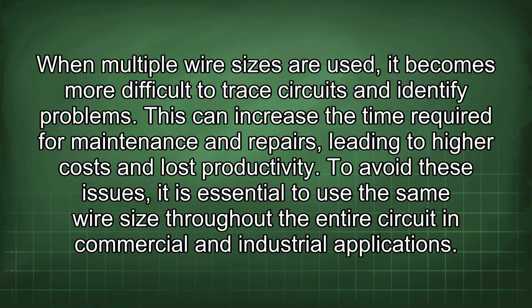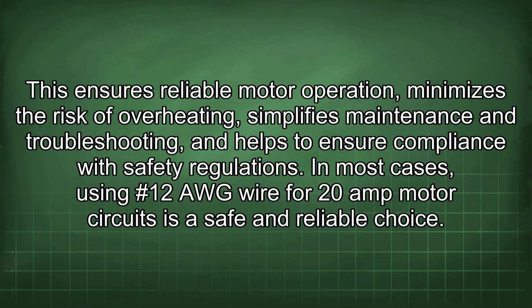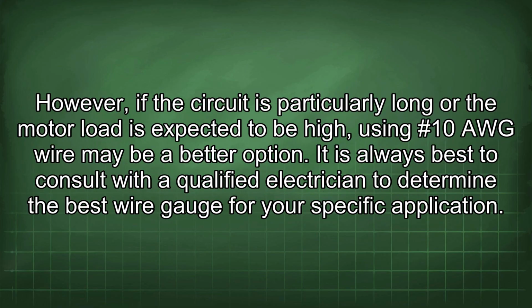To avoid these issues, it is essential to use the same wire size throughout the entire circuit in commercial and industrial applications. This ensures reliable motor operation, minimizes the risk of overheating, simplifies maintenance and troubleshooting, and helps to ensure compliance with safety regulations. In most cases, using #12 AWG wire for 20 amp motor circuits is a safe and reliable choice. However, if the circuit is particularly long or the motor load is expected to be high, using #10 AWG wire may be a better option. It is always best to consult with a qualified electrician to determine the best wire gauge for your specific application.